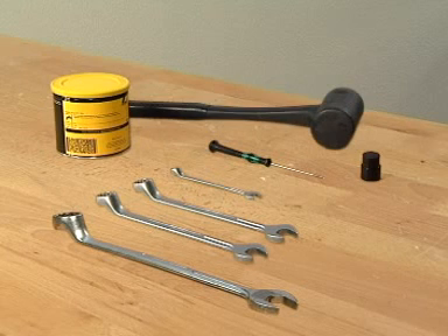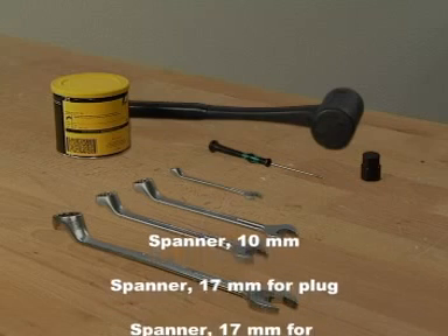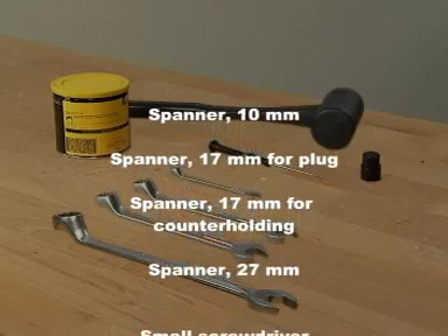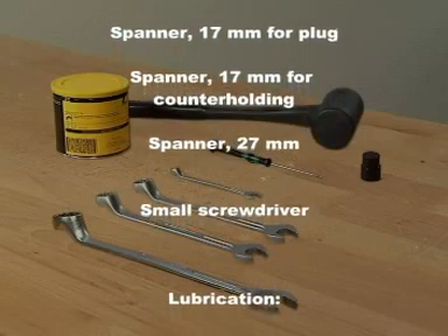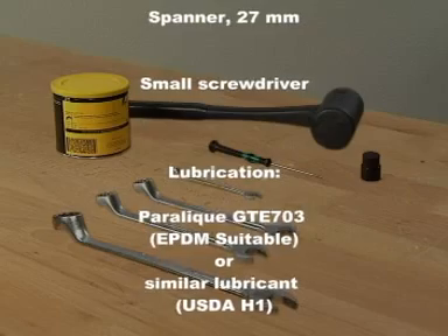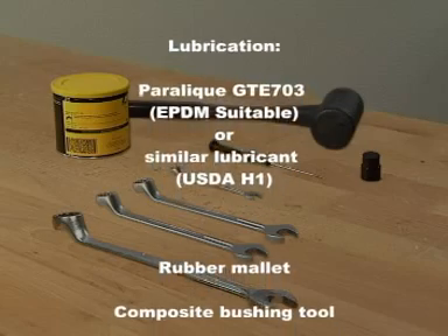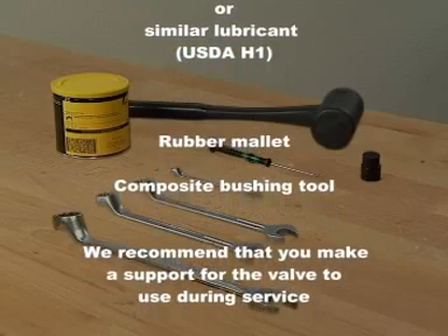The tools required for doing maintenance on the unique SSV valve are: spanner size 10 for the clamp, spanner size 17 for the plug, spanner size 17 for counter-holding the actuator stem, spanner size 27 for the actuator bushings, and a small screwdriver for removing the plug seal and releasing the air behind the plug seal. Lubrication: Paralique GTE703, EPDM suitable or similar lubricant, USDA H1. A rubber mallet for the composite bushing tool.